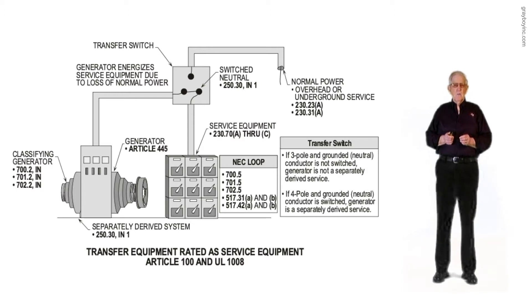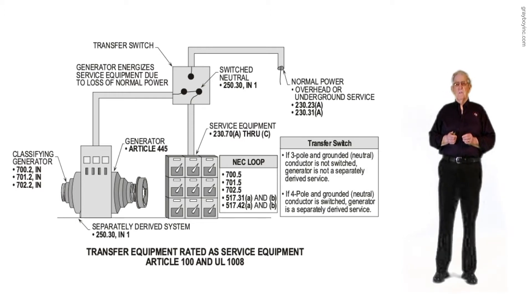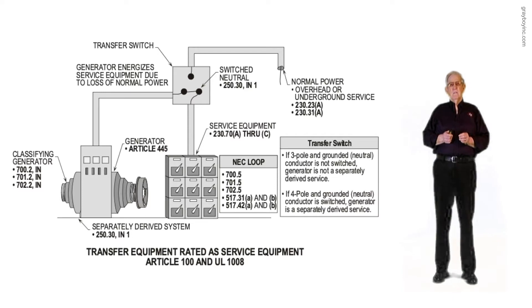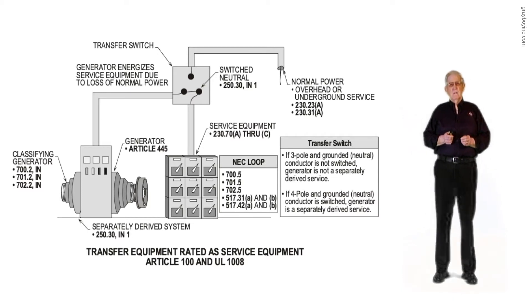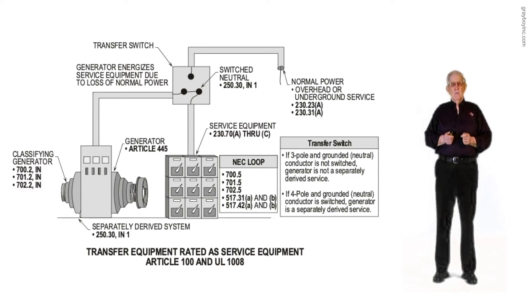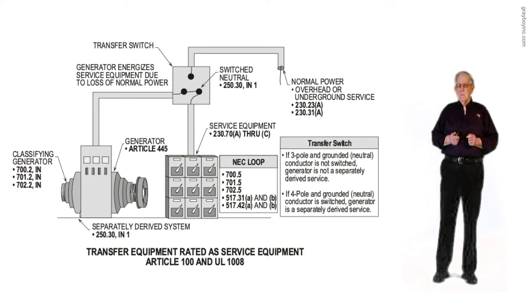If it's a 701.2 generator, then it could be brought on within 60 seconds and have a 15-minute delay characteristic. But notice if it's an emergency generator under 700.2, you can't mix the wiring with the general wiring of the facility.